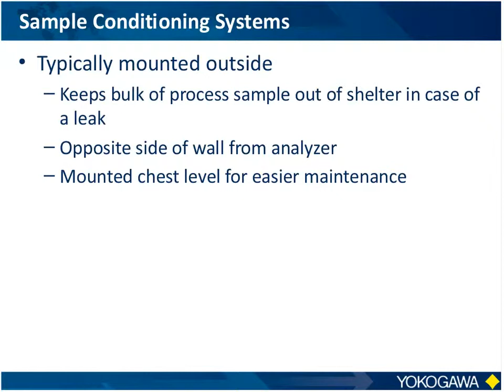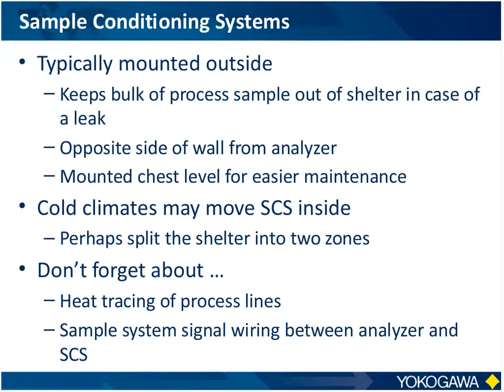Of course, if it's a cold climate, you might not have that option. But when the sample system is mounted on the outside, you need to make sure that you don't forget about heat tracing the tubing between the outside and the inside, and also to make accommodations for the wiring if you're trying to do the package yourself. But it's critical that when you do the sample system that the design is done properly. You got to make sure that, again, as I mentioned, the temperatures and the pressures and the flows are all compatible with the analyzer so that it can operate properly. And most analyzers require some type of zero and span calibration or validation gases, and there needs to be some type of mechanism for switching all of this in so that once a day or once a week the equipment can be calibrated, and that all needs to be done in the sample system.